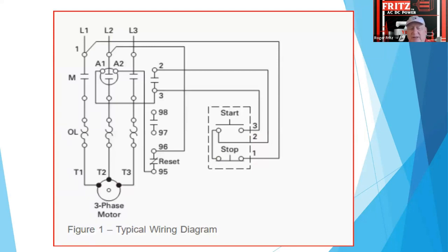So the original electric motor was simply, you had L1, L2, and L3, which are here where your lines are. These show the contactors. These were the thermal overloads, and then it hooked to the 3-phase motor. With the start-stop circuit, it turned the coil on and off and closed these contacts. As soon as you did that, you're putting 230 or 480 volt, depending on how you have the motor connected, directly to the motor.